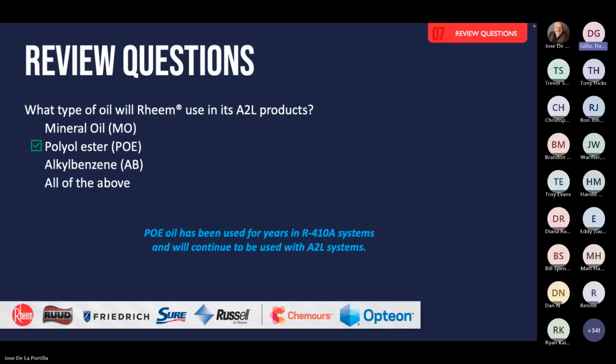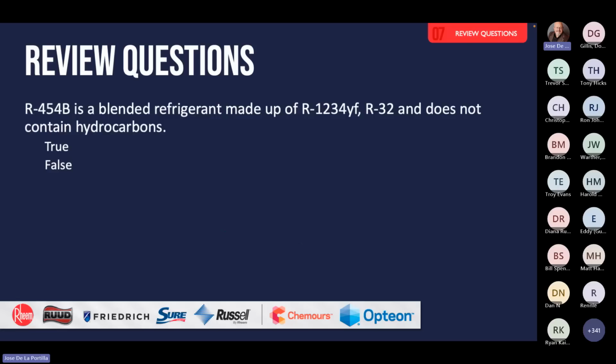Okay? Thanks. Awesome. And the next question: R454B is a blended refrigerant made of R1234yf and R32, and it does not contain hydrocarbons. Is that true or false? Well, the answer is true. And if you want the mixture, remember it's a zeotropic blend with a very low glide of 1.4 degrees Fahrenheit, and it's 68.9% R32 and 31.1% R1234yf.